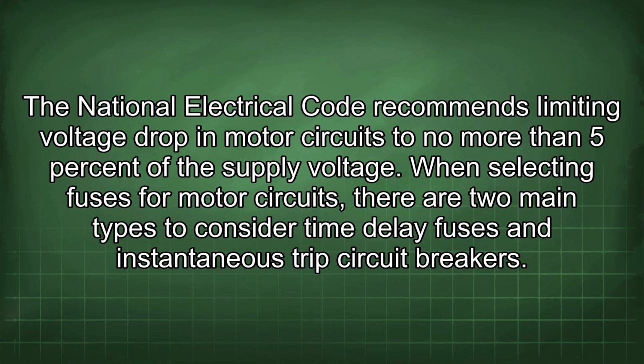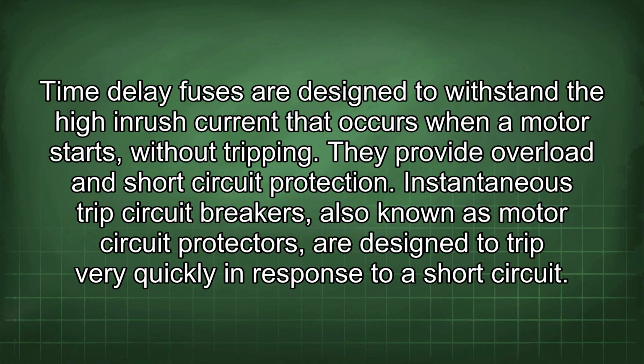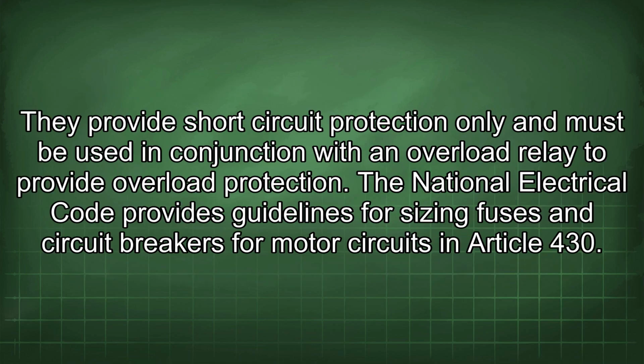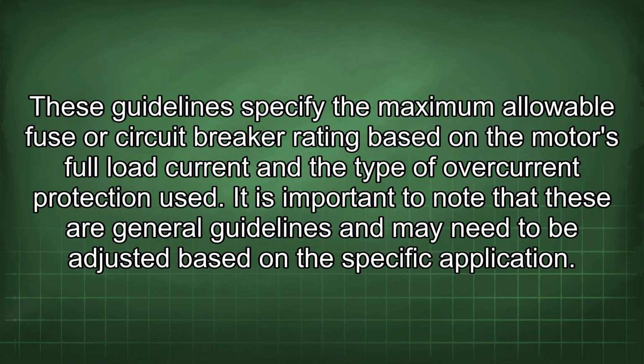When selecting fuses for motor circuits, there are two main types to consider: time delay fuses and instantaneous trip circuit breakers. Time delay fuses are designed to withstand the high inrush current that occurs when a motor starts without tripping. They provide overload and short circuit protection. Instantaneous trip circuit breakers, also known as motor circuit protectors, are designed to trip very quickly in response to short circuit. They provide short circuit protection only and must be used in conjunction with an overload relay to provide overload protection. The National Electrical Code provides guidelines for sizing fuses and circuit breakers for motor circuits in Article 430. These guidelines specify the maximum allowable fuse or circuit breaker rating based on the motor's full load current and the type of overcurrent protection used.